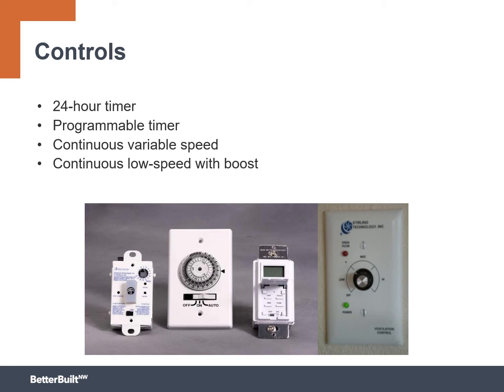Some of the controllers you see on this screen, particularly the one on the far left and the 2 on the right, have the ability to run continuously at a low rate in the background, and still have the ability, you push the button or twist the knob or dial, and it can go to a higher speed for when you need spot ventilation. So in your bathroom, maybe you have 2 fans and they're each running 30 CFM in background mode.